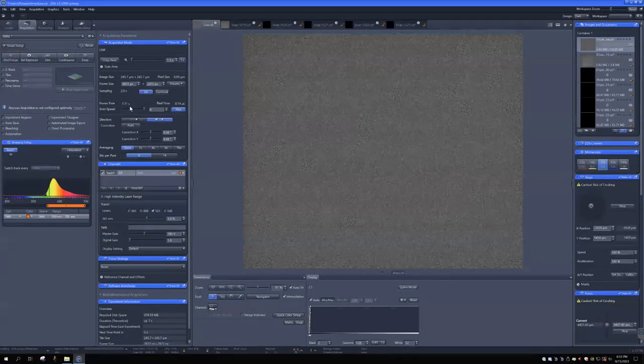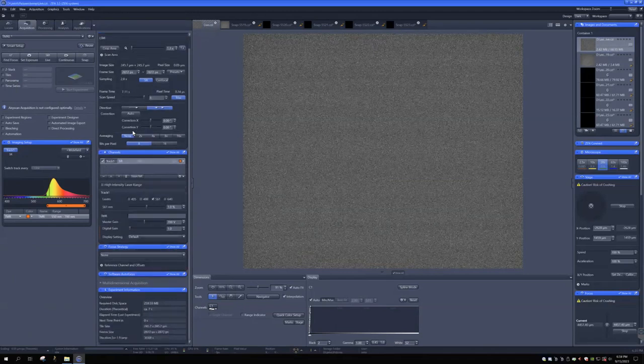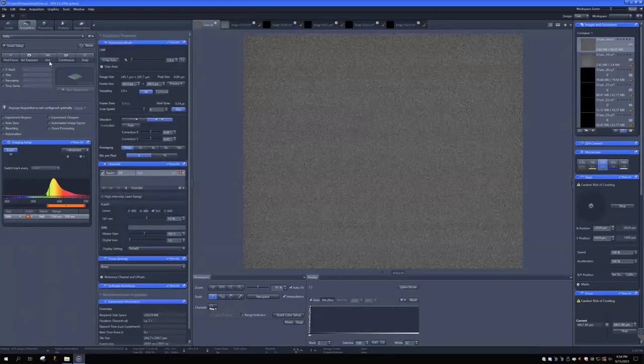The frame time is telling you that if you're taking one image of this size, it's going to take 7.11 seconds. And our channel, right now we have the TMRE setting here. The laser we use is 561. Laser intensity is set to 1%. Master gain is just for the image display performance. This master gain can be used ranging from 700 to 900. Right now we'll just keep it as default. And then, everything is set up, we just do a live imaging.